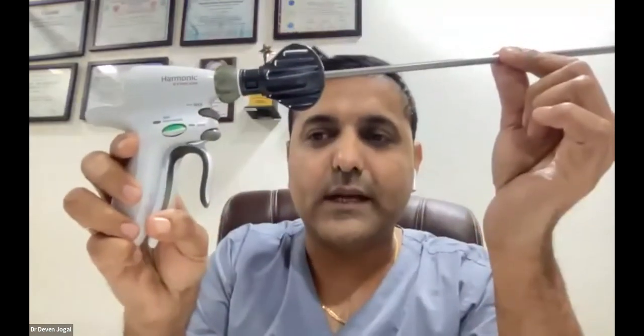Secondly, you use it for dissection. For dissection, you don't require to press it completely. That's the tip. So if, let's say, I'm using it for this tissue, I don't have to press it completely. Even this much of compression is fine, so your pad will remain for a longer time and you can use it for maybe 12, 15, 20, 25 surgeries, provided the cleaning and sterilization process is good.